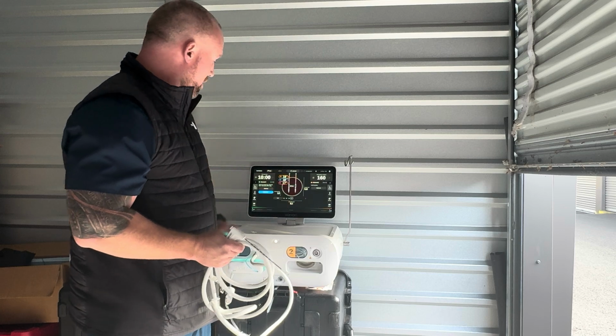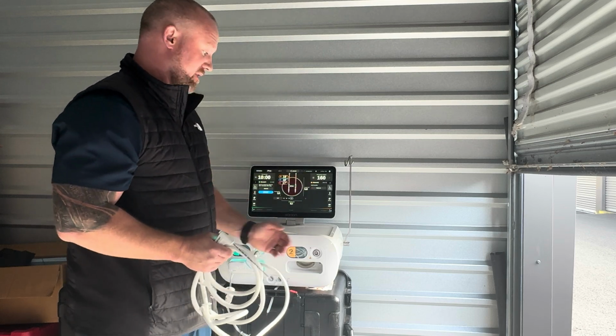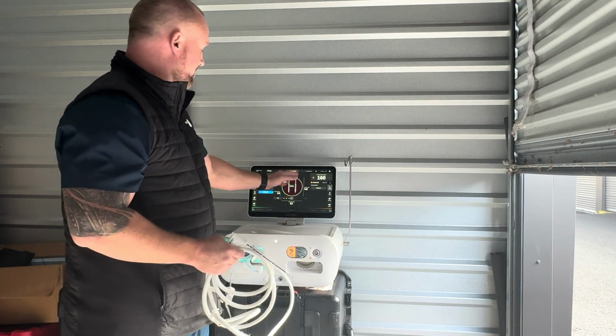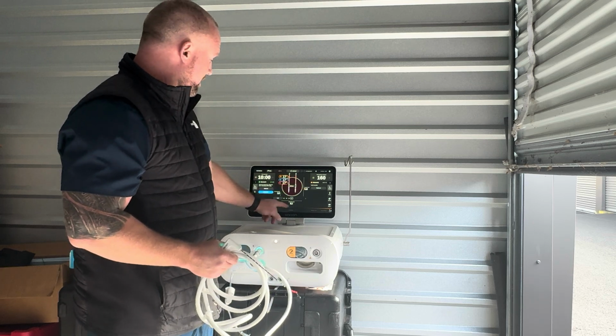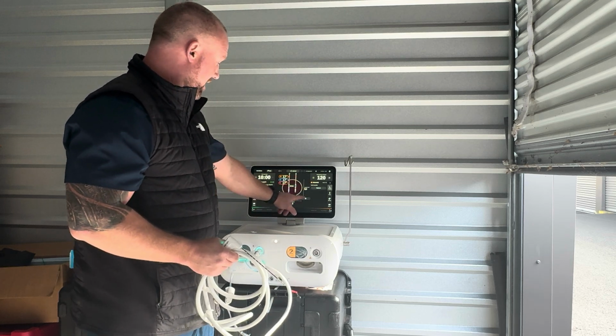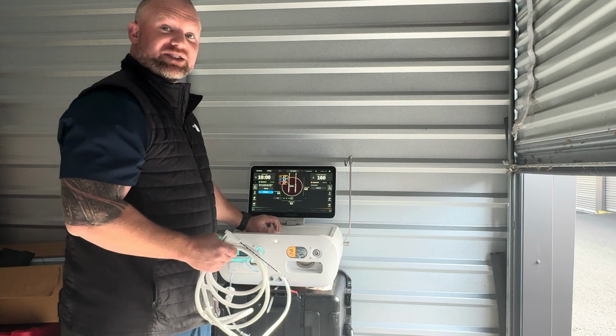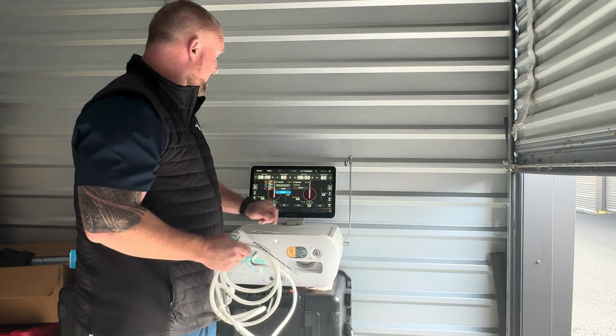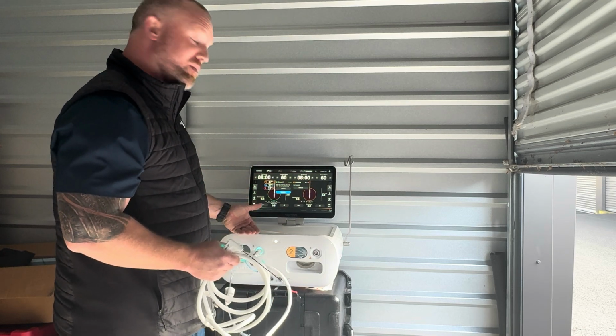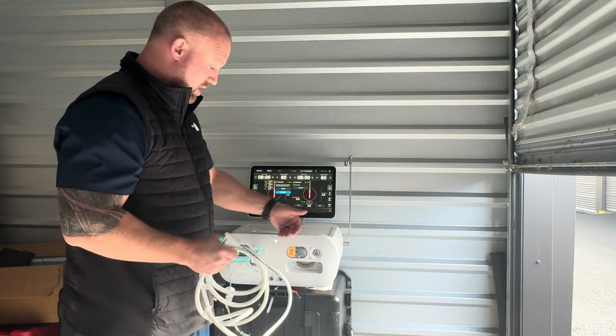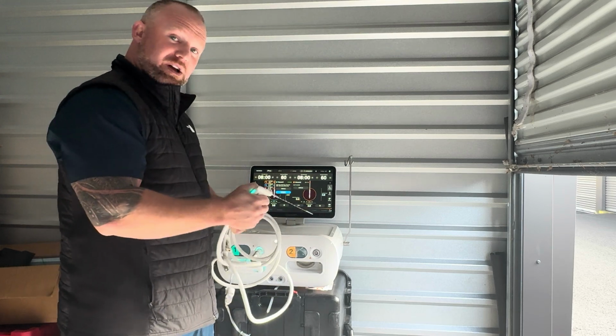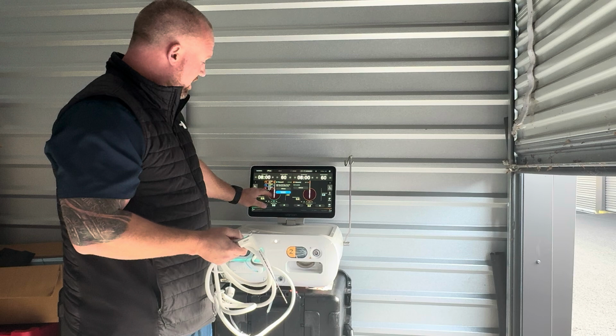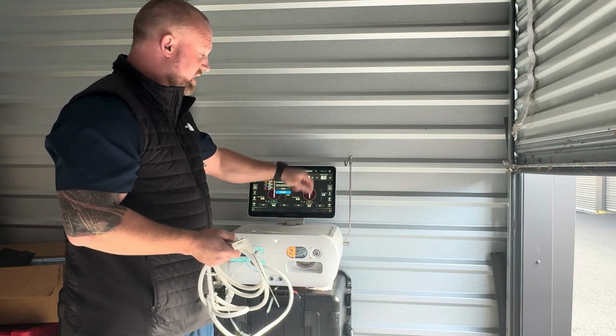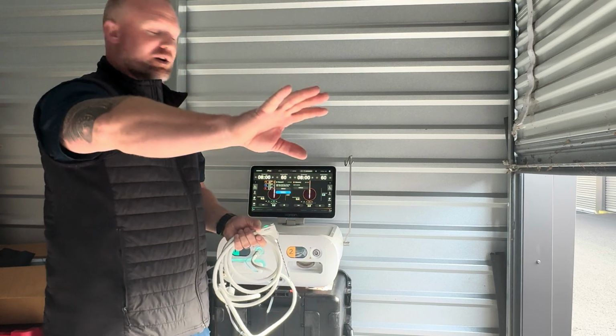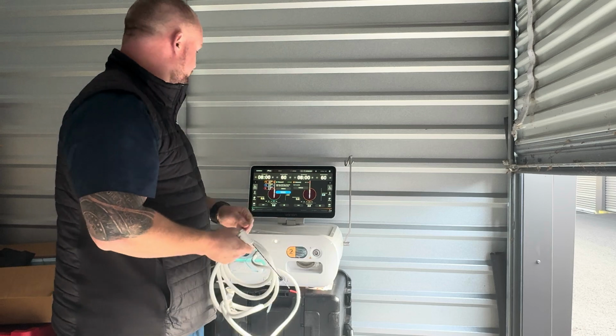Again, if we have another probe, it's going to do the same thing. It's telling us right now there's not a probe in number 2, so it's not going to let us do anything, but it will show you the size of the ablations we can get, all the way up to around a 6x6 centimeter burn. Again, these are the independent ones, so we have probe 1 in. If we wanted to start an ablation with this one, get the ablation going, hit start, we can actually reposition this needle, put a needle in, and start that for a completely different second needle.